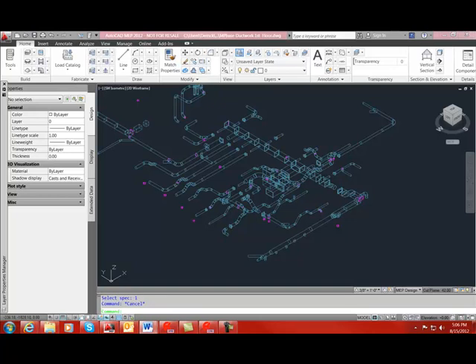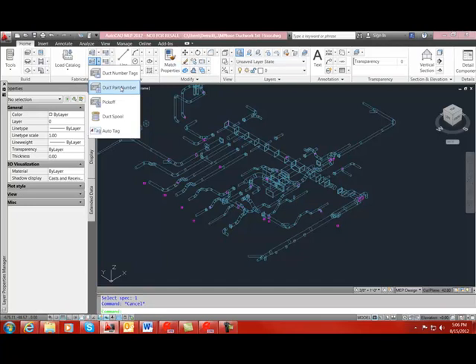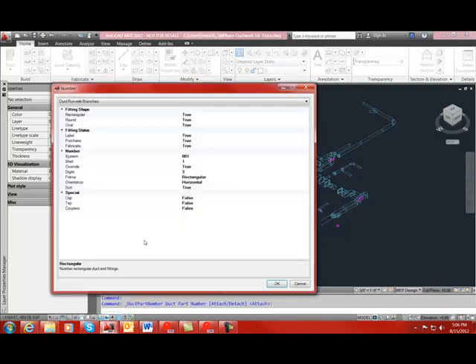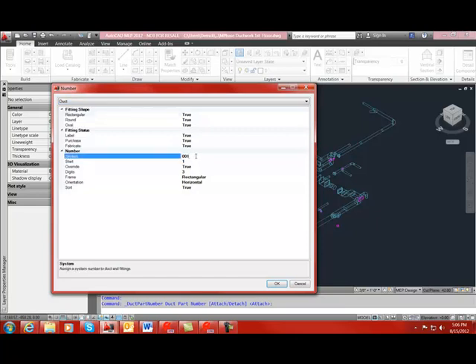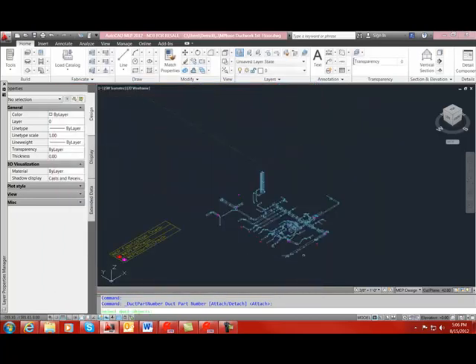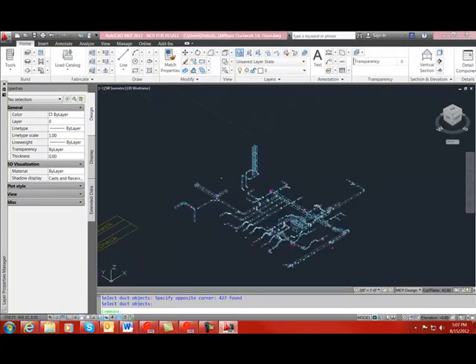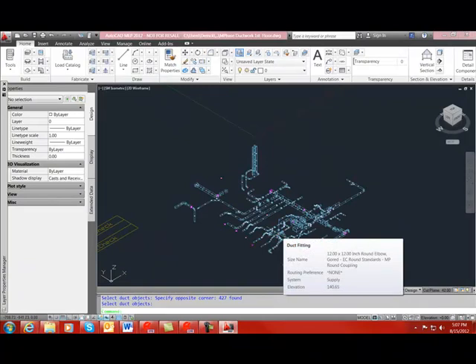Once you are satisfied with the systems, you will want to number the duct and duct fittings. To do that, we are going to go to the middle duct drop-down and select Duct Part Number. Click Enter to attach. There are a lot of options available for numbering the duct, but for this video, we will just make sure that the duct selection method has been chosen, and we will enter a system name for the system that we are numbering. We are going to select Duct from the drop-down, then switch the system name over to Supply. Click OK, select all of our ductwork, and click Enter. Now we are going to review our duct numbers to make sure that the duct is numbered as we would expect.